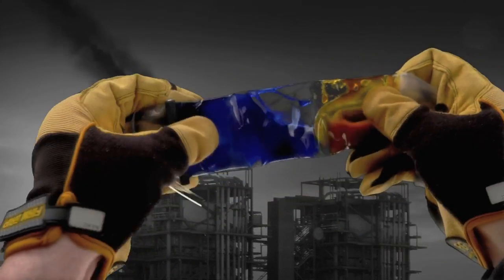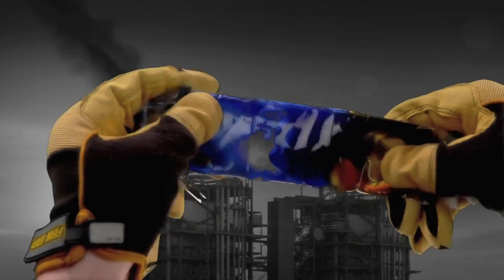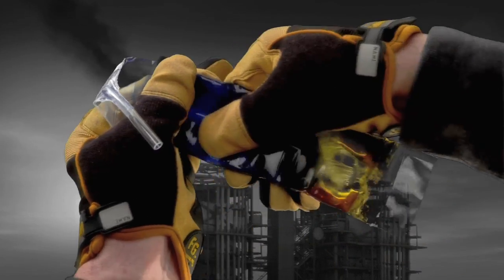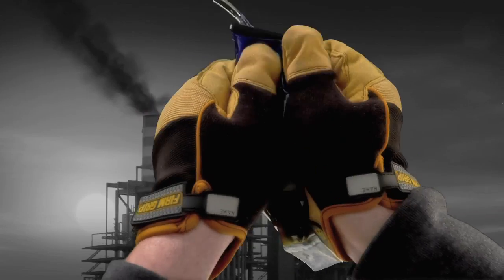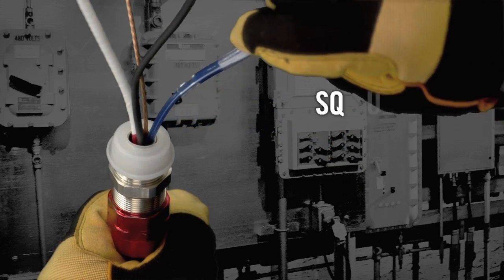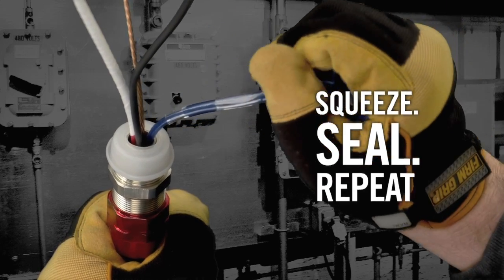With RapidEX liquid resin seal, you can create a barrier seal in a fraction of the time. Simply mix the two-part resin together in its applicator pouch. There's no mess. Then pour the resin in and around the conductors using the applicator tip.